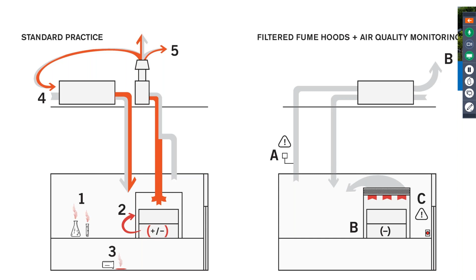In addition, we're using filtered fume hoods that chemically adsorb the chemicals in the fume hood onto an activated carbon filter, and then returning clean air back to the space. And this is a technology that's been around for almost 50 years. We've used it in many of our projects now. There's hundreds of applications throughout the Boston area. So between those two strategies, we've actually provided a healthier, safer environment that also dramatically reduces the energy consumption for the building.